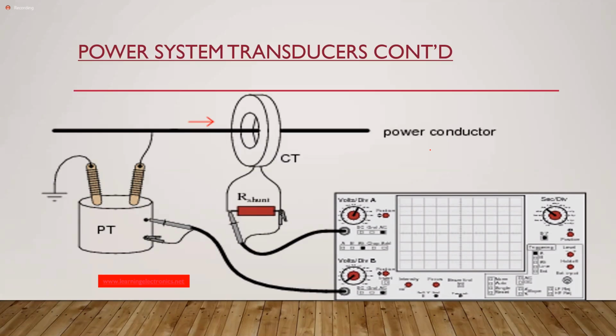Now, a voltage transformer, we're not going to get into it, but I think I did mention it last week in the introduction. I said that voltage transformers are very large. In terms of cost, they cost almost as much as your power transformer. So whilst we were speaking about redundancy for your protection system, we said that you would not necessarily find the VT repeated. We'll have one set of VTs that's used in several areas, because they are very expensive and they are huge. So you'd have your VT there, giving you that standard output. And of course, you have CTs, let's just say, all over the place.